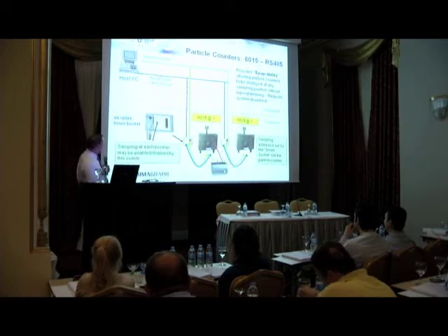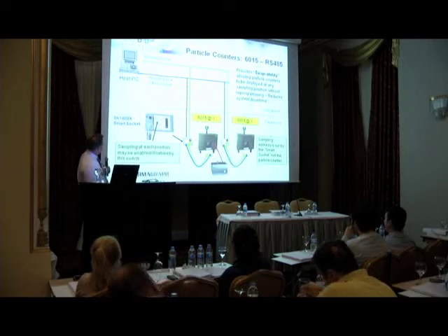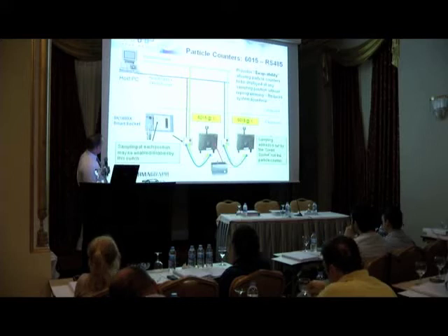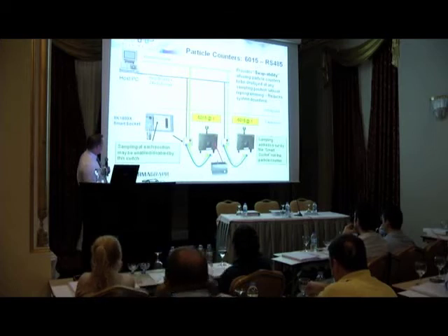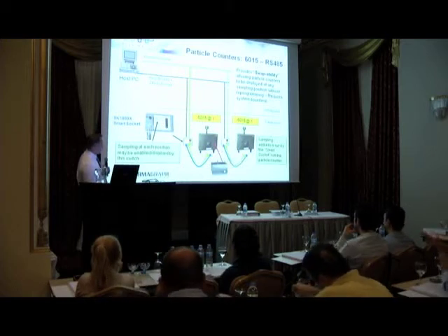It's the same thing again, just a slightly different counter. Previously we were using Ethernet, here we're using RS485. I don't want to go into that too much, but the only difference here is with Ethernet, each counter has an IP address and the address stays with the counter.